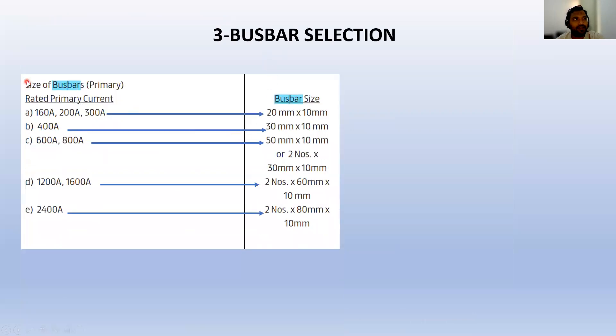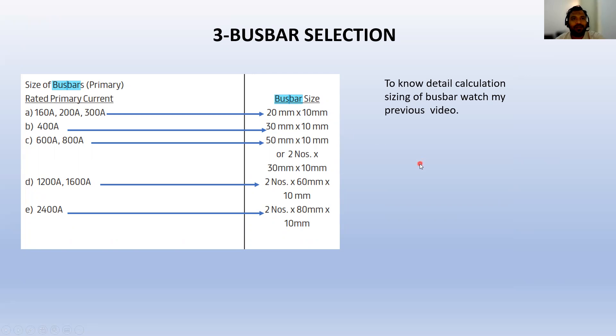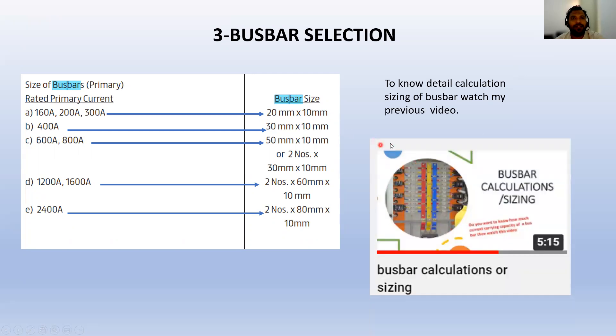For bus bar selection, the standard sizes are: 160–200A = 20mm × 10mm, 400A = 30mm × 10mm, 600–800A = 50mm × 10mm or two 30mm × 10mm bars, 1200–1600A = two 60mm × 10mm bars. For detailed bus bar calculations and sizing, refer to the dedicated bus bar calculation video.